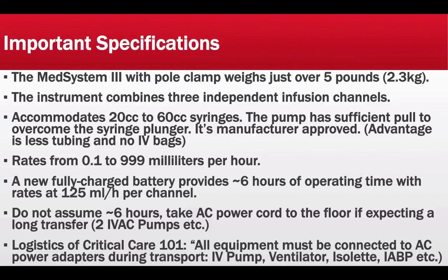The manufacturer actually approves its usage and for this modality. And the advantage obviously is less tubing and no IV bags to lug around with you. Rates range from 0.1 to 999 mLs per hour, and this will depend on the modes you're in. So if you're in neonatal mode, it will only go from 0.1 to 99.9 mLs an hour. And if you're going to be in general purpose 2 or operating room, it will give you a greater range of modes. And I'll have a chart of all those modes in this presentation.